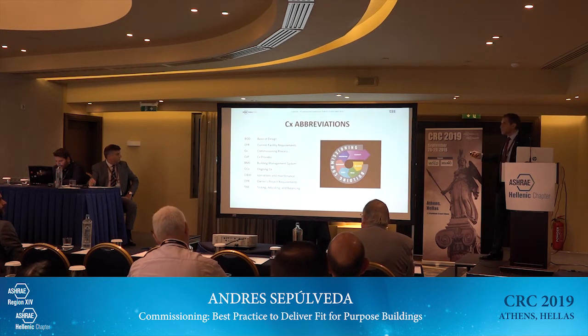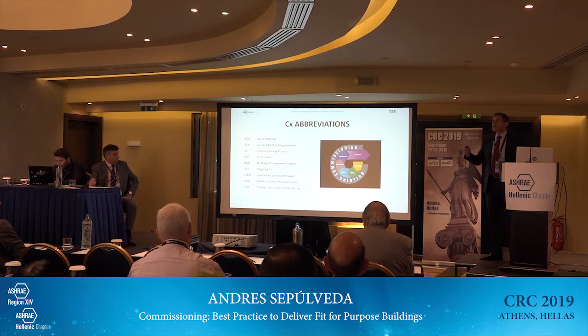CX stands for commissioning process. Commissioning provider - that's a change in commissioning terminology. Before, it was commissioning authority, commissioning agent, or in the UK commissioning manager, but now, thanks to the influence of ASHRAE, the term CXP, commissioning provider, is very much accepted.